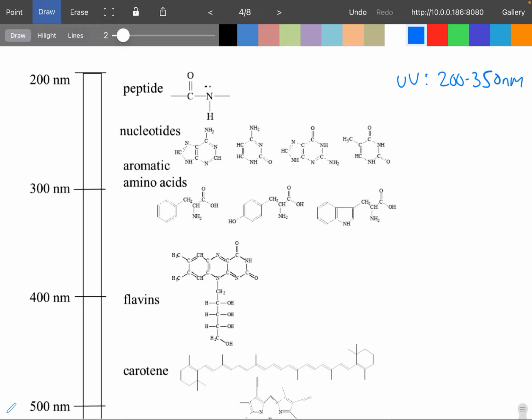nanometer range for that. The thing about UV is it's not always super safe, right? So you can't shine it on your face, can't shine it in your eyes, so there are some precautions that have to be taken when we're talking about UV, and most of the time the instrument takes care of those issues. Another downside to UV is that it requires quartz cuvettes. And so plastic and glass and things like that absorb UV wavelengths. And so if we're doing anything with UV, we have to have the appropriate cuvettes.